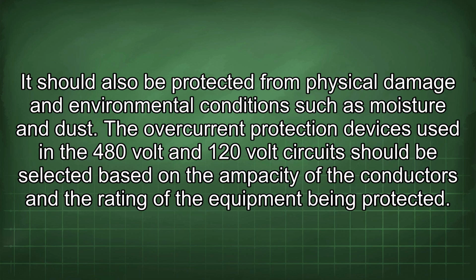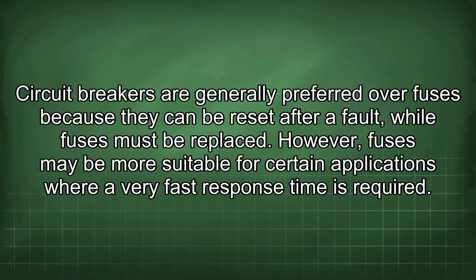The overcurrent protection devices used in the 480 volt and 120 volt circuits should be selected based on the ampacity of the conductors and the rating of the equipment being protected. Circuit breakers are generally preferred over fuses because they can be reset after a fault, while fuses must be replaced. However, fuses may be more suitable for certain applications where a very fast response time is required.